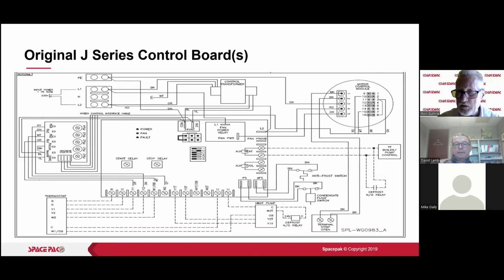Now, another thing that I want to point out here is that on the terminals on the bottom of the board, we see some T terminals, Y1T, Y2T, W2T. Those T terminals need to be used. We want to wire to the board from the thermostat, and then we want to wire to the outdoor unit through the T terminals. If we use those terminals, we're protected by the freezestat. If we don't, we're not protected by the freezestat. So that's one thing to keep in mind if you're looking at one of these J series units. Make sure that the outdoor units are wired through those T terminals on the board there.